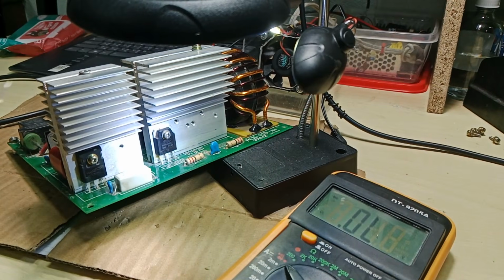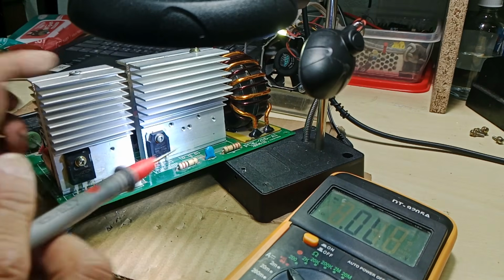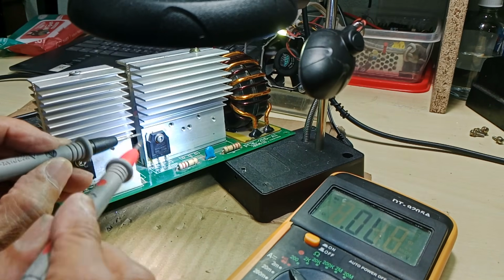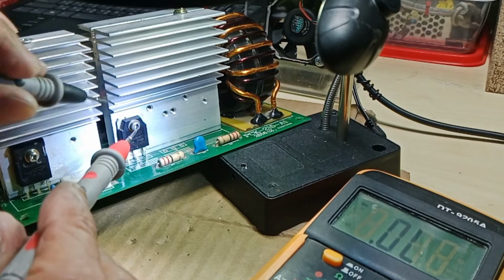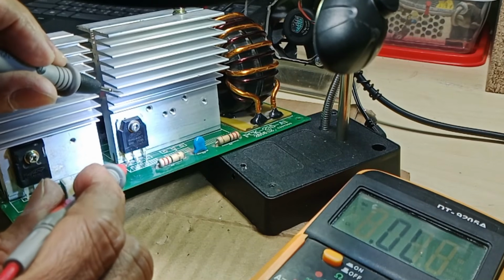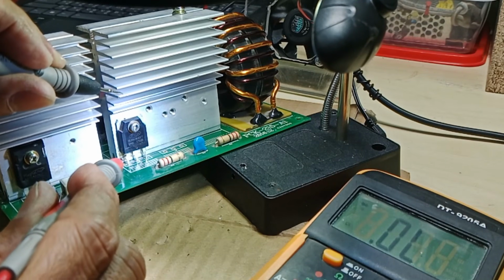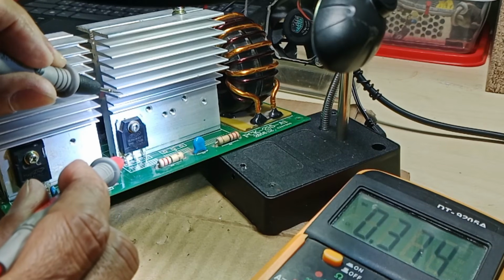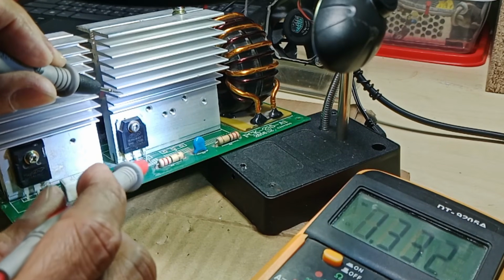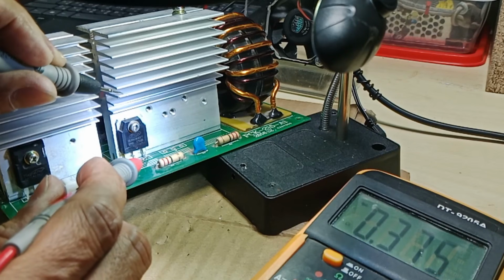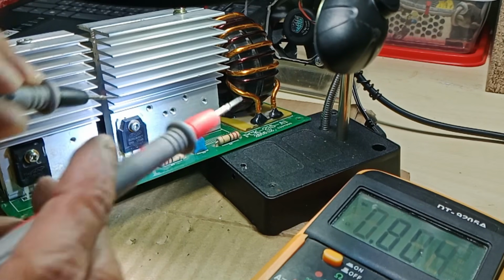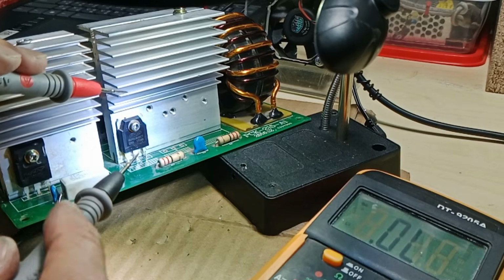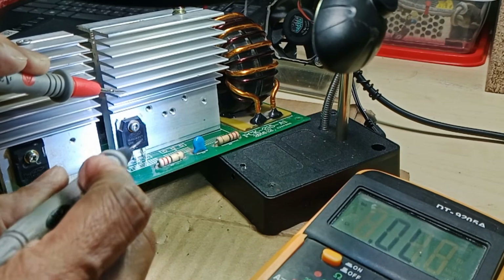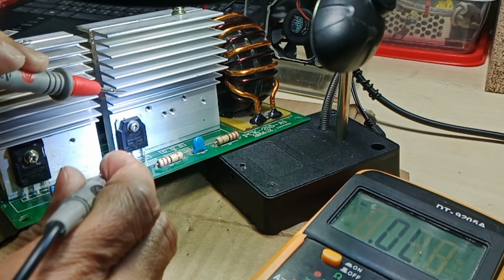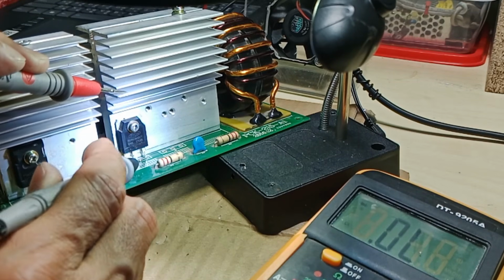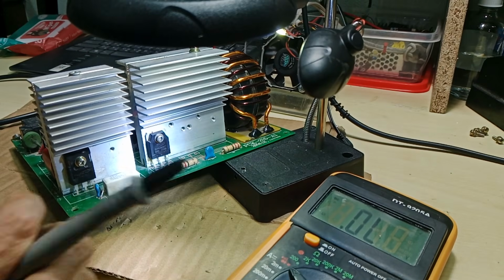I then test the fast recovery diodes. When the black probe is on the cathode, which is electrically connected to the heatsink, and the red probe on the anode, we are getting the diode voltage. When I reverse the polarity of the probes, we get OL, or open lead, on the multimeter. That is how it should be, meaning the diode is good.